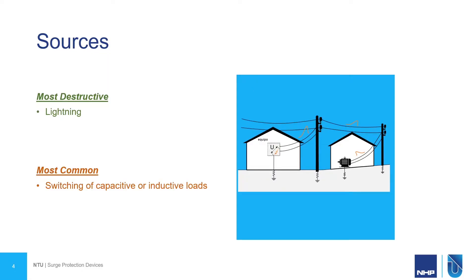The most common type of surge seen on a network comes from switching of capacitive and inductive loads — things like DOL starters, welders, switching of capacitive banks. Electrical accidents on the network can all cause a spike in voltage, as can things like cloud-to-cloud lightning.